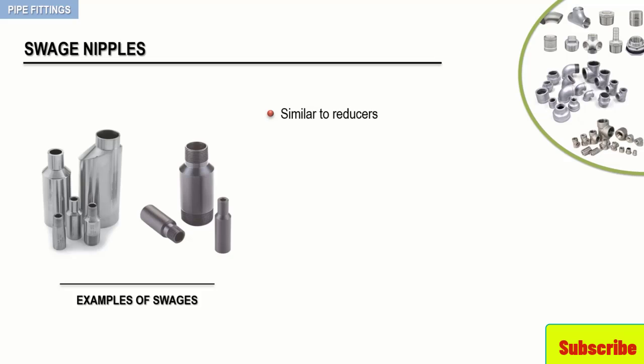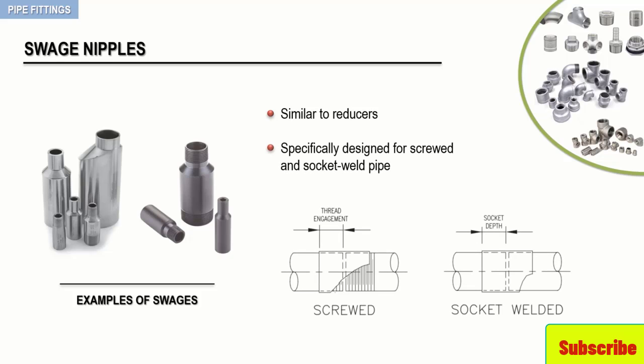Swages are specifically designed for screwed and socket weld pipe. Screwed swages have external threads and are connected directly to other screwed fittings without the need of a pipe nipple. Like reducers, they are available in either a concentric or eccentric shape, as depicted here.